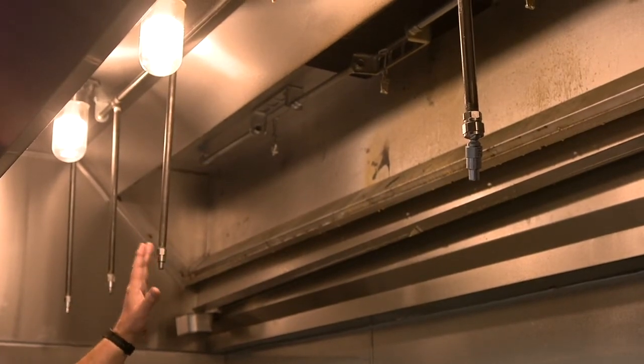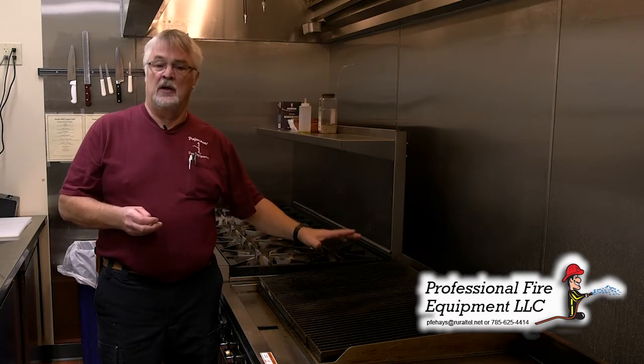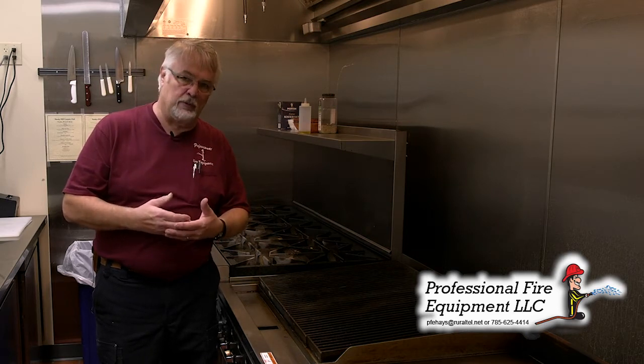At the same time, we're going to shut the fuel off to it, whether it's gas or electric. So we not only extinguish the fire, we cut off any fuel source. The chemical, when it comes down, is going to mix with your grease. It's going to saponificate. That's a foam that causes a layer of non-flammable material between your grease and your outside air. The liquid system is also going to cool the grease down below the flash point so that it won't reignite. At the same time, we're going to shut the supply air off so that we don't bring in any air to feed a fire.